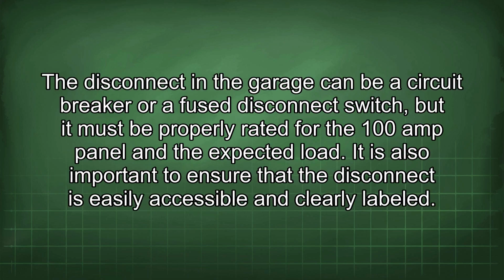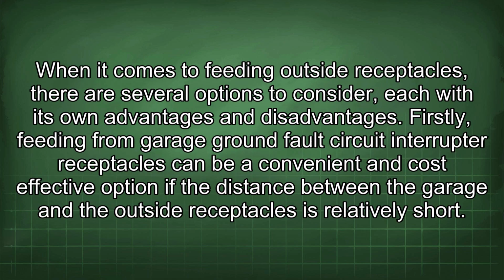The disconnect in the garage can be a circuit breaker or a fused disconnect switch, but it must be properly rated for the 100 amp panel and the expected load. It is also important to ensure that the disconnect is easily accessible and clearly labeled. When it comes to feeding outside receptacles, there are several options to consider, each with its own advantages and disadvantages. Firstly, feeding from garage ground fault circuit interrupter receptacles can be a convenient and cost-effective option if the distance between the garage and the outside receptacles is relatively short.